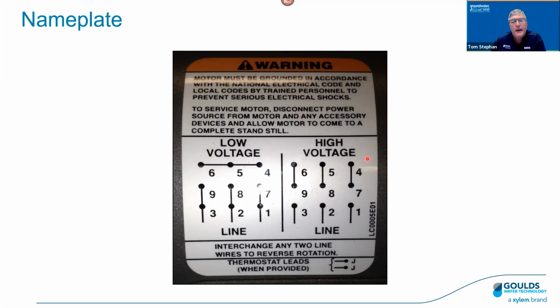We'll just take a quick peek at high. And again, in this case, that would be 460, right? So we take 6 and 9, put those together, wire nut those off, 5 and 8, put those together, 4 and 7, put those together. So then we take 1, 2, and 3, connect those to your 3 different legs, right? And so in other words, for high, if I look at a wire nut, I should see no less than 2 wires for each wire nut.